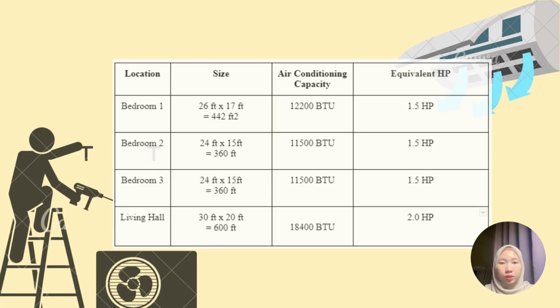We show the air conditioning capacity and the equivalent HP value that we get from the calculation. For bedroom 1, we got 12,200 BTU capacity and the equivalent value is 1.5 HP. For bedrooms 2 and 3, we got 11,500 BTU and the equivalent is 1.5 HP. And lastly, for the living hall, we got 18,400 BTU, which is 2.0 HP.